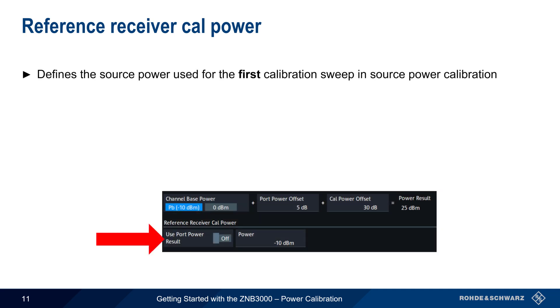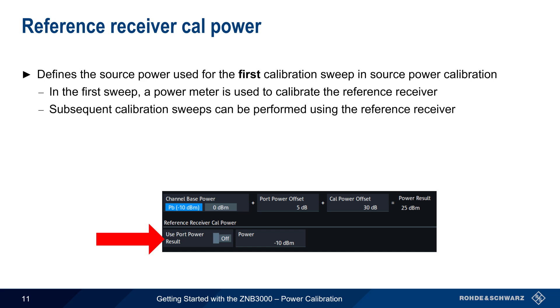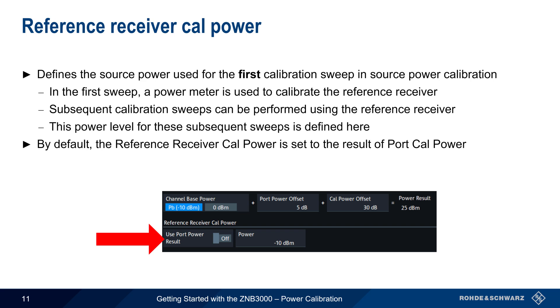Underneath the channel base power settings is reference receiver CalPower, which defines the source power to be used for the first calibration sweep in source power calibration. An RF power meter or sensor is used during this first sweep to calibrate the reference receiver. Subsequent calibration sweeps can be performed using only the reference receiver, and reference receiver CalPower defines the power level for these subsequent sweeps. By default, the reference receiver calibration power is set to the result of the port power calibration.